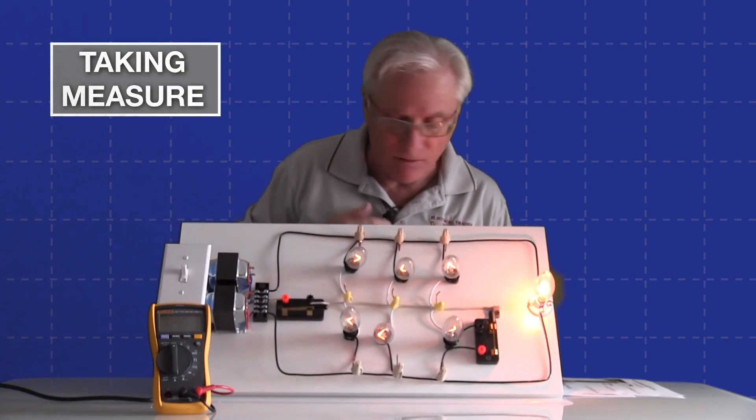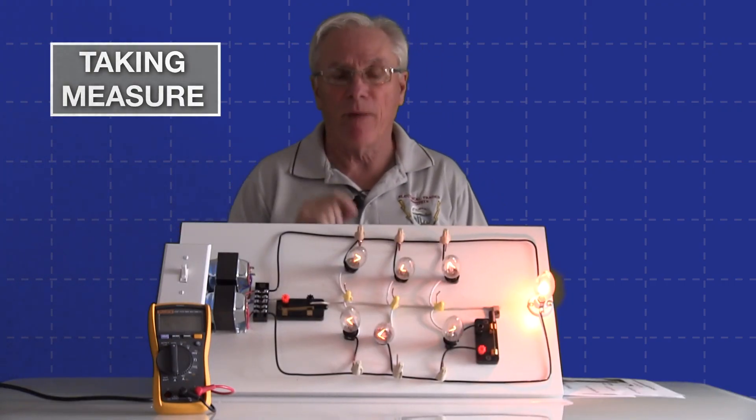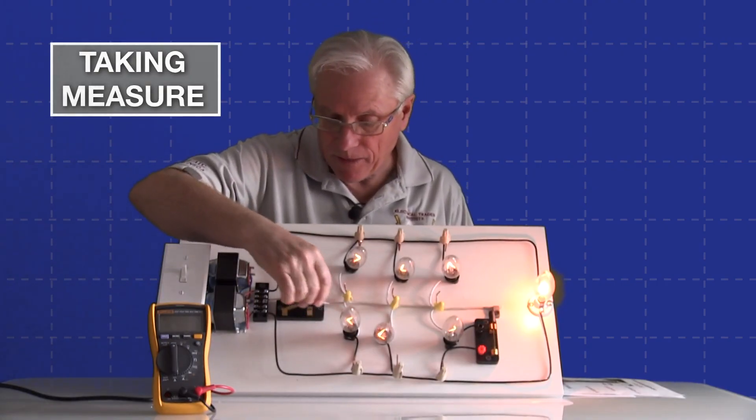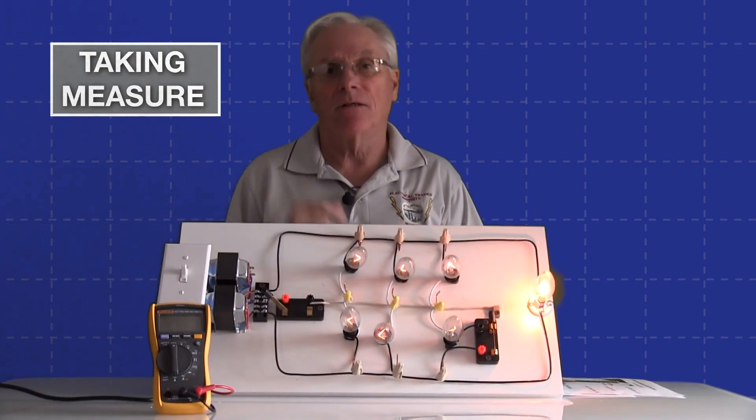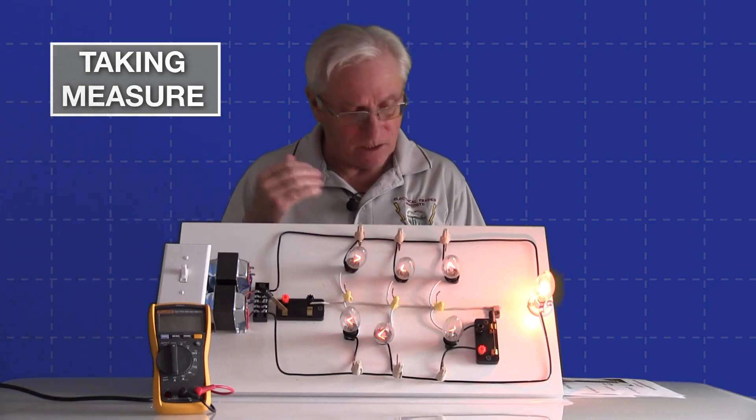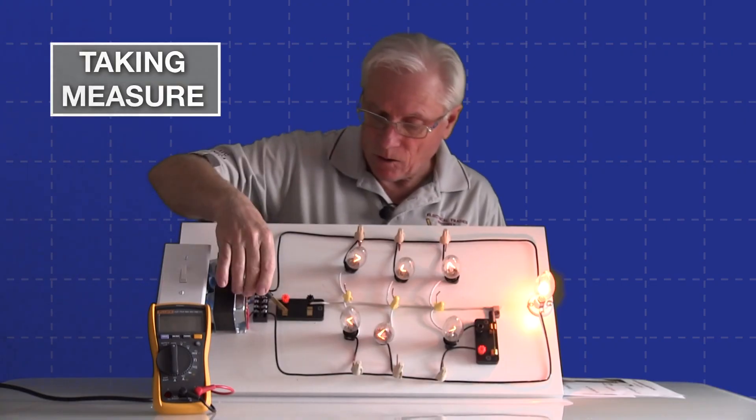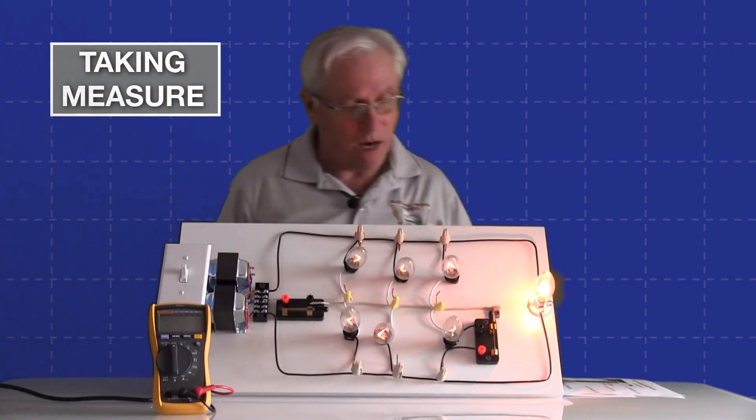The neutral is in the middle and this is each side of our 240. In a perfectly balanced load like this, I can open up the neutral and it still functions just fine because it's all balanced out and not creating any voltage imbalance.